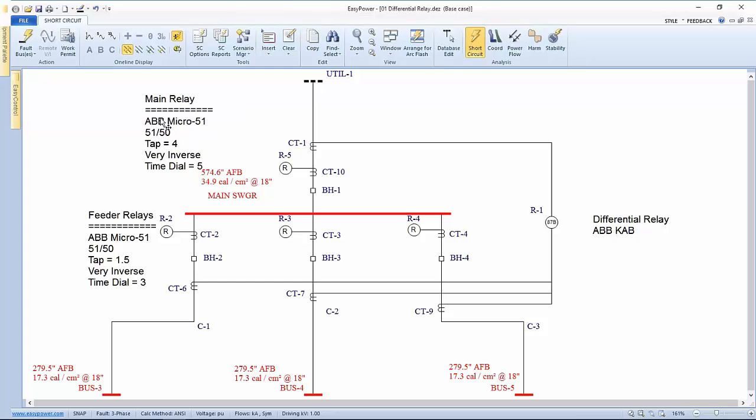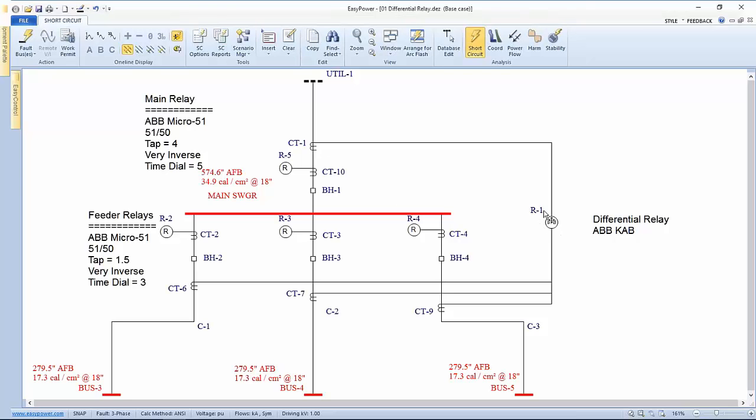Let's just go in and look at the specifics. If I go into short circuit and fault all my buses, you can see that I have essentially some fairly high incident energy at each of the buses. There's a need if these buses require someone to work on them while they are energized, there's some need for some other device or some other method of bringing down these energies, especially if we have an arcing situation.